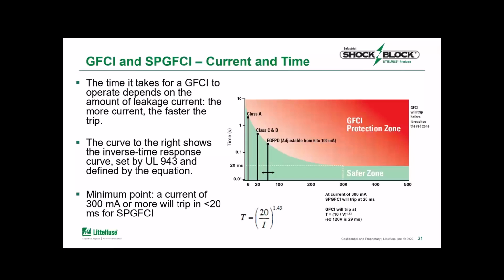Now, we show on the screen there the EGFPD, and that's just a reference. Littelfuse also offers these equipment ground fault protection devices, and they are still built to these same standards and have the same protection curve, but they have adjustable pickup levels. Because of that, they're not considered GFCIs or special purpose GFCIs, but I just wanted to mention them because they can help meet code requirements for heat tracing, de-icing, and marina circuits where those 30 to 100 milliamp sensitive pickup levels are required, but a GFCI may not be mandated.